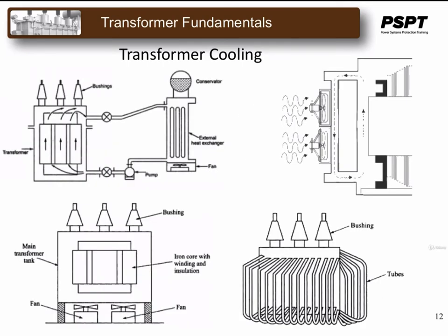The main source of heat generated in a transformer is its copper losses, or its I²R losses. Although there are other factors contributing to the heat in a transformer, such as hysteresis and eddy current losses, the contribution of the I²R loss dominates all of them.